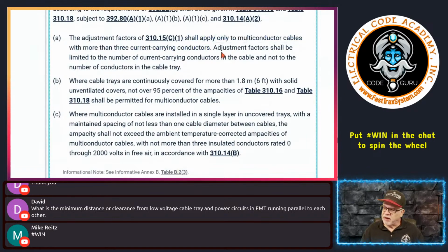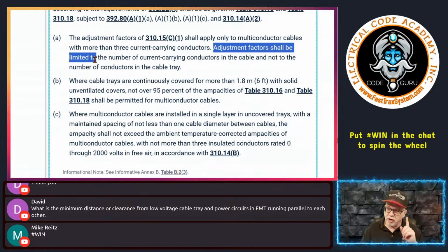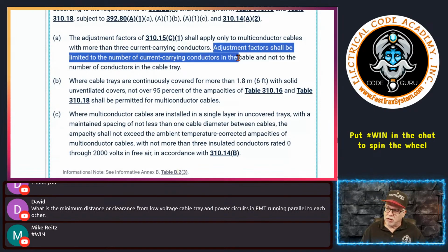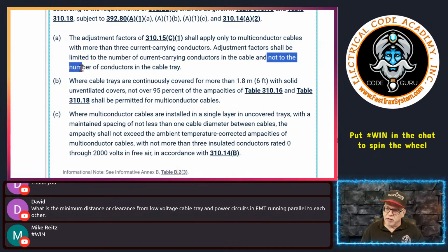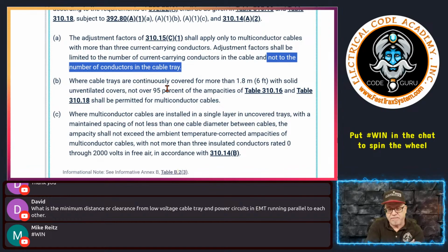It says adjustment factors, the ones we just talked about right here, shall be limited to the number of current carrying conductors in the cable and not to the number of conductors in the cable tray. Okay, so that's important first, right? Because that is basically telling me that as long as my multi-conductor cable does not have more than 3 current carrying conductors in it, I can ignore 310.15(C)(1), right? I can just say, forget about it.